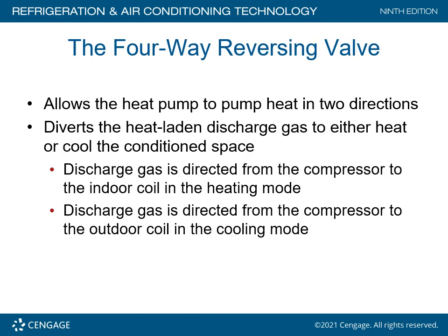The four-way reversing valve. This thing can be a little bit complicated. We'll hopefully take some of the mystery out of it as we get into this lesson. It allows the heat pump to pump heat in two directions, diverting the heat-laden discharge gas to either heat or cool the conditioned space. Discharge gas is directed from the compressor to the indoor coil in the heating mode. Discharge gas is directed from the compressor to the outdoor coil in the cooling mode. Now, notice that we do not refer to the outdoor unit as a condensing unit. We refer to it as the outdoor unit, and we refer to the air handler as the indoor unit.